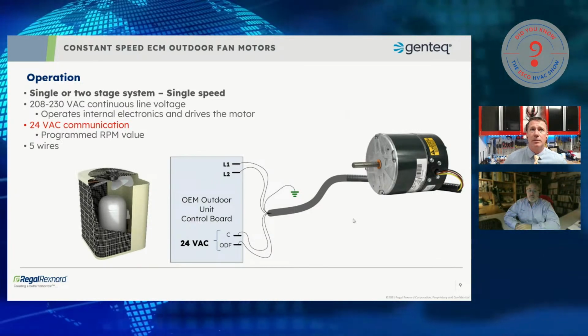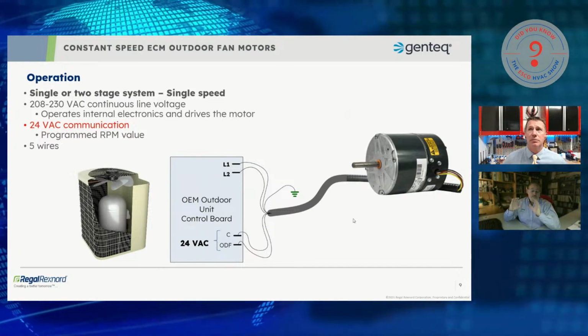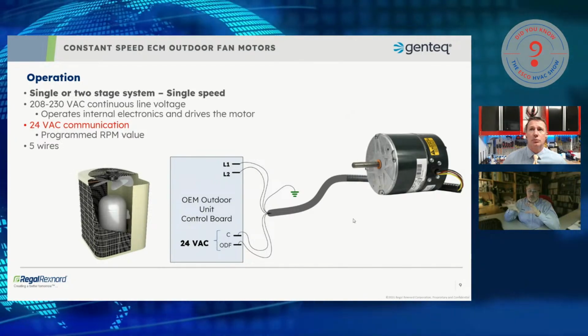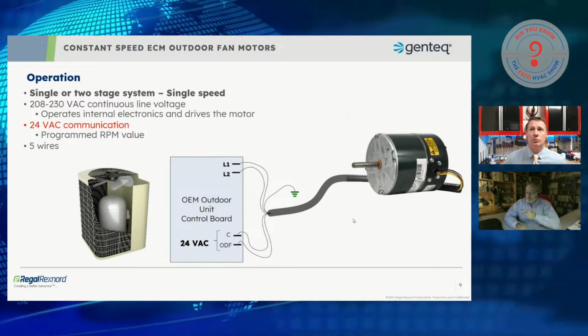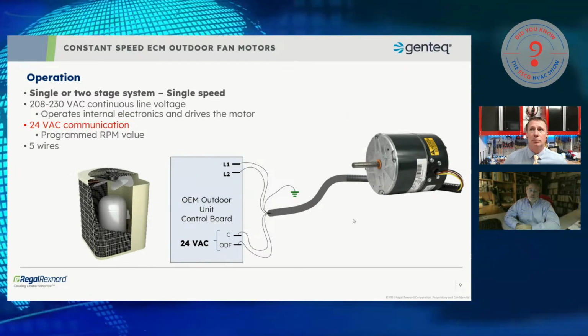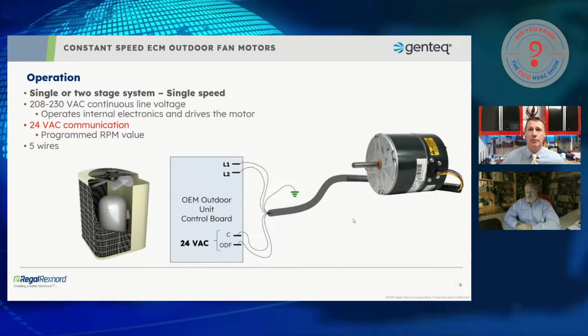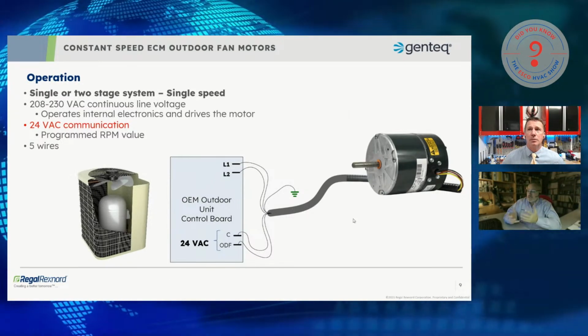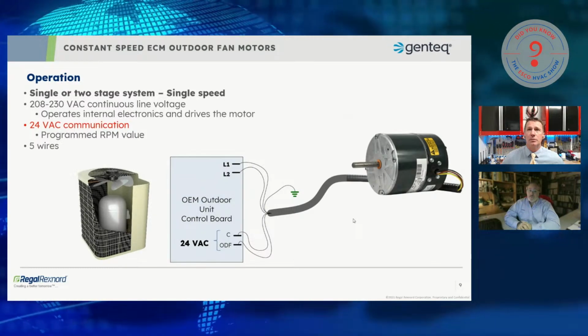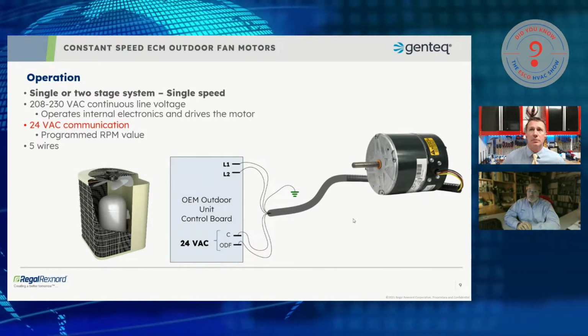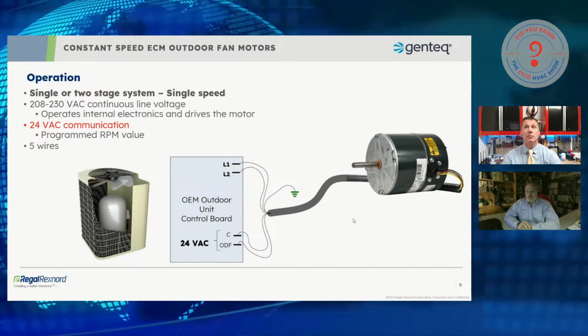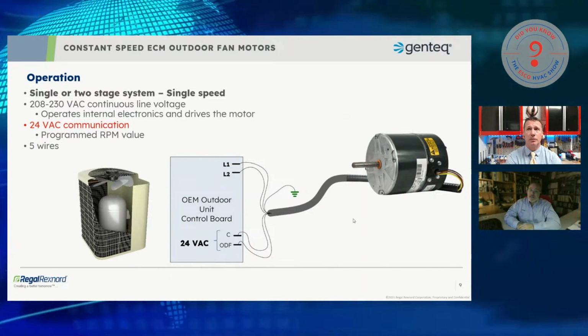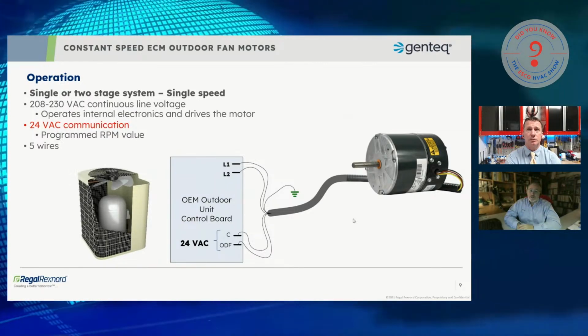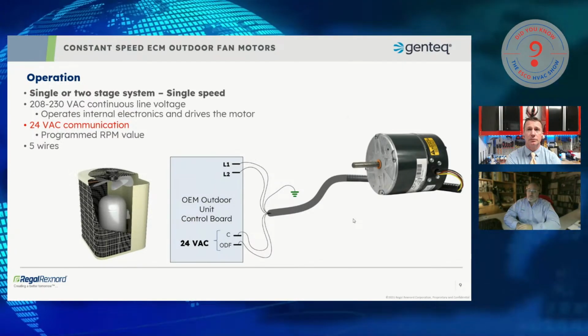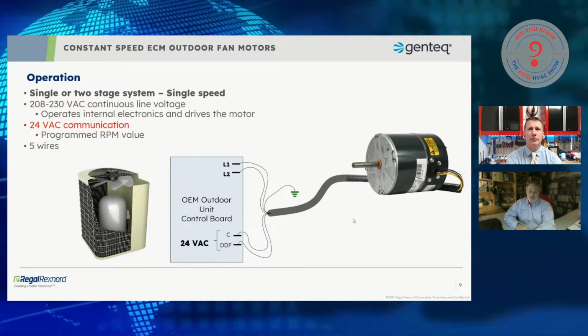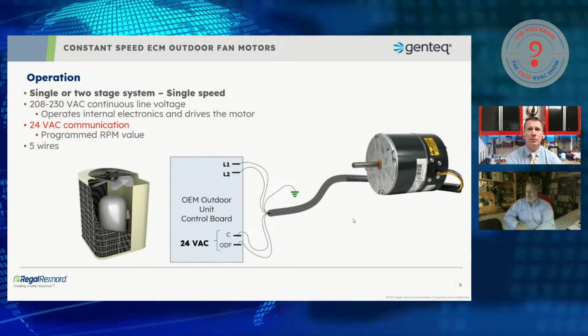The only thing that really changes for that motor is, my engineers are probably cringing when they hear this, but I can reduce this whole complex motor to a simple relay. It's looking for 24 volts on that 1 wire to turn on and do what it's programmed to do. When that 24 volts goes away, the motor turns off. So once you understand how that motor works, especially in 24 volt discrete mode, it's a very simple motor to diagnose. Very efficient. It's not as easy to understand what RPM it should be running at if you're having refrigeration side challenges. But as far as the motor being on or off, it's pretty simple when it's using 24 volt speed or speed taps. That's not proper English there. Sorry.